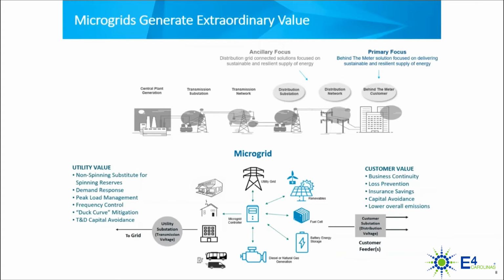For peak load management, we have a microgrid system in Yuma, Arizona at the Marine Corps Air Station, working with Arizona Public Service, that responds to frequency dips or fluctuations on the distribution feeder serving the base. As frequency moves, our microgrid responds accordingly, able to start up and push power in to maintain frequency levels, or absorb power in over-frequency situations.